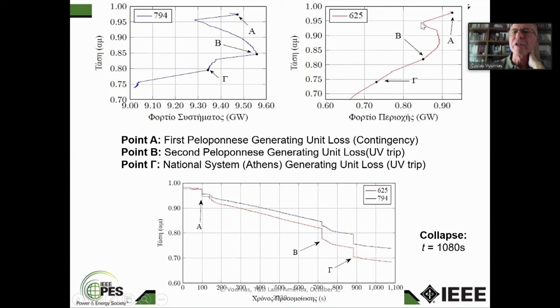You see the loss of the first unit. It increases the consumption, but then voltage drops more than the increase of consumption. And you cannot reach this point, which means that the system will continue requesting more and getting less until the second unit is lost, and then the third unit is lost, and the system collapses.